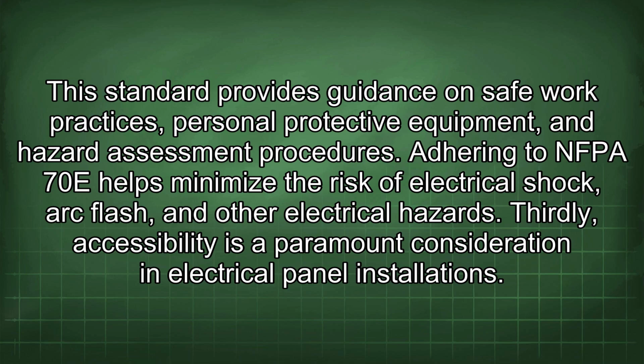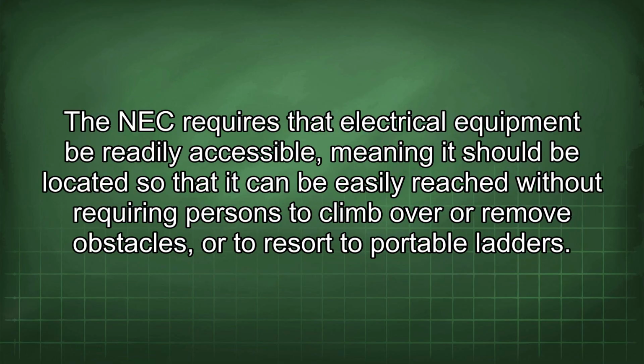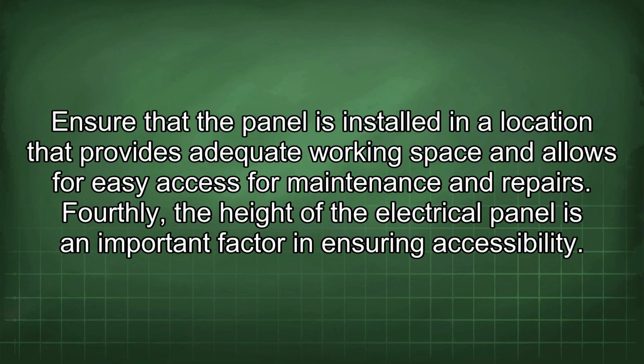Thirdly, accessibility is a paramount consideration in electrical panel installations. The NEC requires that electrical equipment be readily accessible, meaning it should be located so that it can be easily reached without requiring persons to climb over or remove obstacles, or to resort to portable ladders. Ensure that the panel is installed in a location that provides adequate working space and allows for easy access for maintenance and repairs. Fourthly, the height of the electrical panel is an important factor in ensuring accessibility.